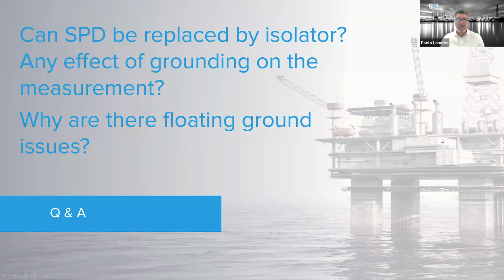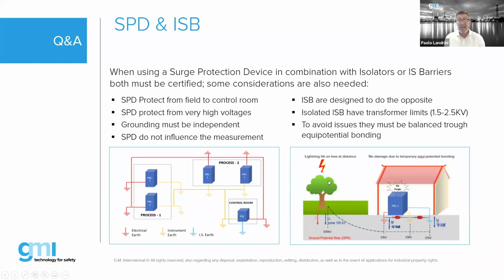So the question is, can SPD be replaced by an isolator? Is there any effect of grounding on the measurement? And why are there floating ground issues? Well, first of all, an SPD is designed to protect from the field to the control room. Instead, a safety barrier is designed to do the very opposite. In addition, an SPD can protect from a very high voltage, kilovolts, 10 kilovolts, some are 20 kilovolts, whereas a safety barrier is designed to limit voltage at max, very much less.